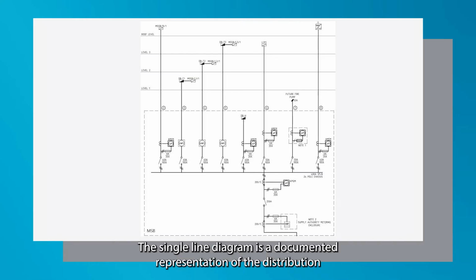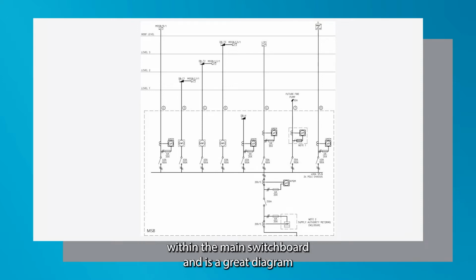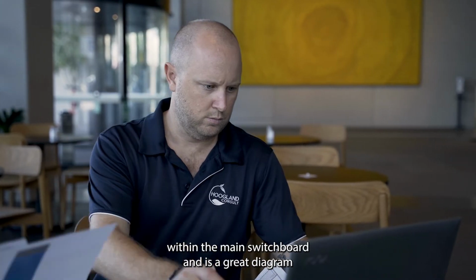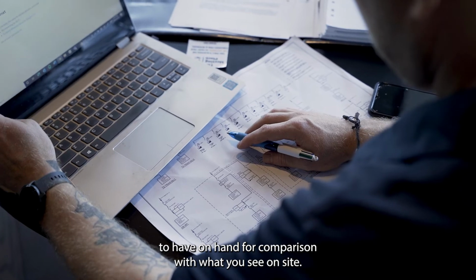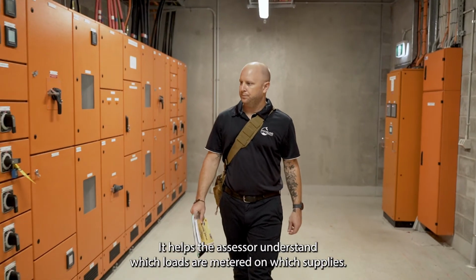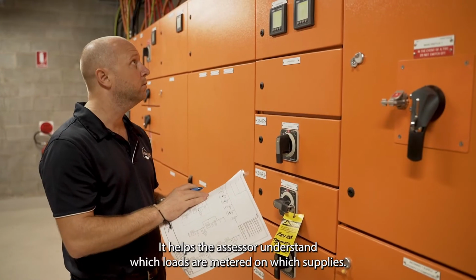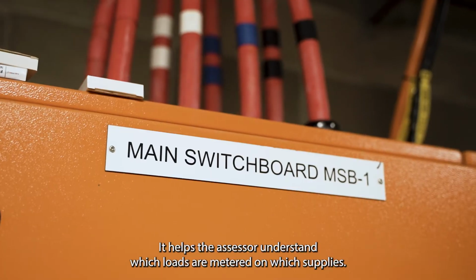The single line diagram is a documented representation of the distribution within the main switchboard and is a great diagram to have on hand for comparison with what you see on site. It helps the assessor understand which loads are metered on which supplies.